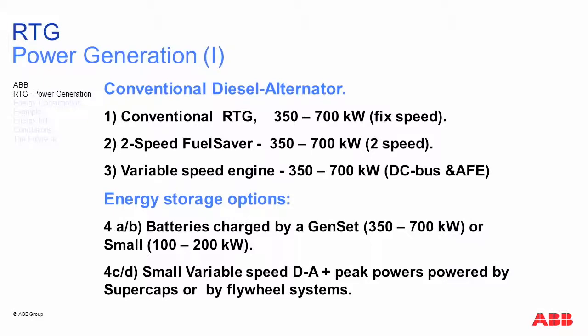We can classify the RTG from the power generation point of view into 3 different types. First is what we call conventional diesel alternator - a fixed speed engine with a fixed speed alternator, with power range of 350 to 700 kilowatts. In this group we also have the 2-speed with fuel saver diesel alternator, same power range - this is an evolution of type number 1.